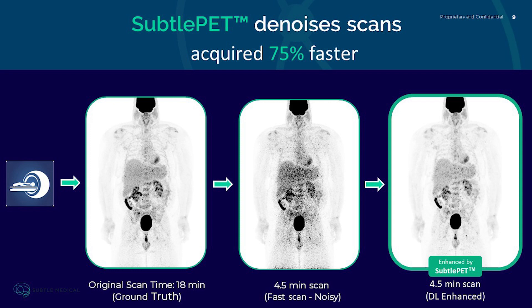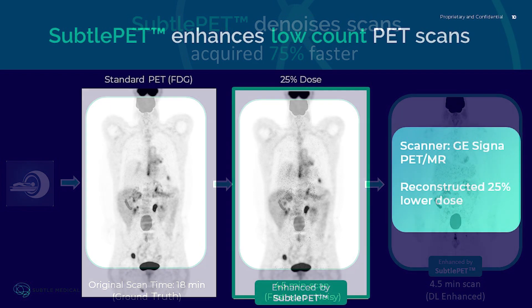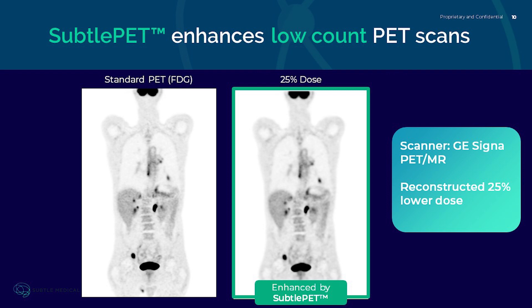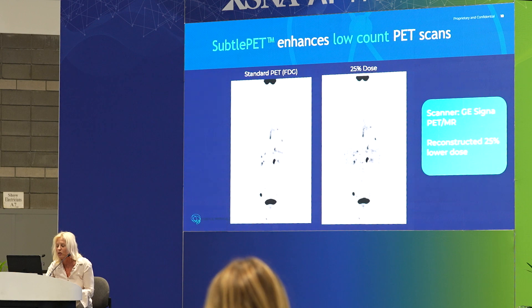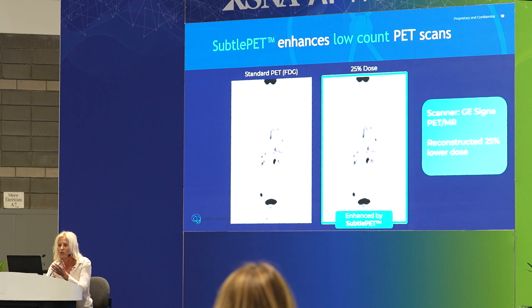Subtle PET denoises scans that are acquired 75 percent faster. Here's the original scan that took 18 minutes — if you alter your protocol and go faster you can get that down to four and a half minutes, but the images are quite noisy. You can then enhance that fast noisy image with Subtle PET, and that deep learning really provides a big boost in the signal to noise ratio. Subtle PET also enhances low count PET scans — we call it a low count scan if you reduce the radiotracer dose or acquire images faster. Looking at this 25 percent reduced dose image on the right hand side, if you enhance that with Subtle PET, that noisy image is transformed into higher image quality.